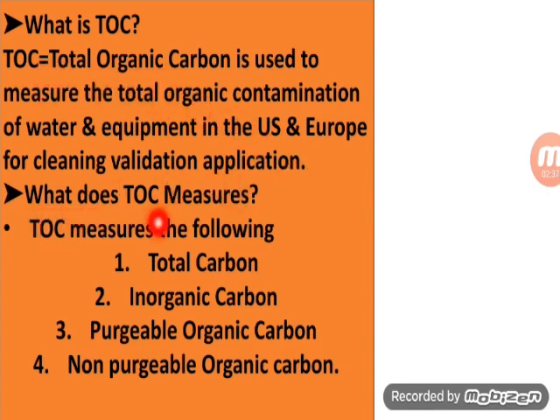TOC measures the following: total carbon, inorganic carbon, purgeable organic carbon, and non-purgeable organic carbon. These are identified in a product and then eliminated from the water after elimination for cleaning purposes — and not only for cleaning purposes, but also for other fields like excipients and WFI (Water for Injection) in particular areas.